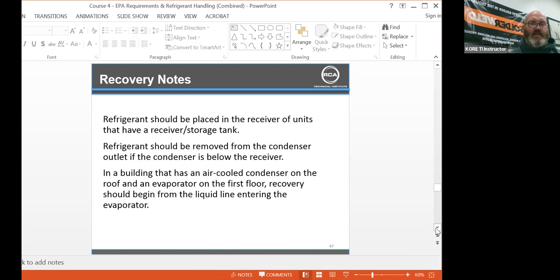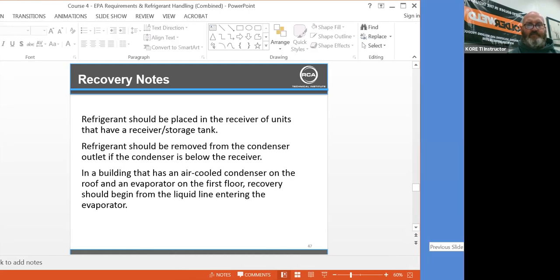In a building that has an air-cooled condenser on the roof and an evaporator on the first floor, recovery should begin from the liquid line entering the evaporator. That's where the refrigerant is going to stack. Usually it's going to stack up against your solenoid valve.